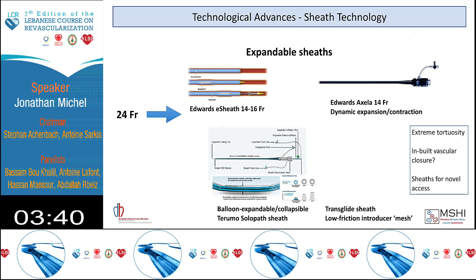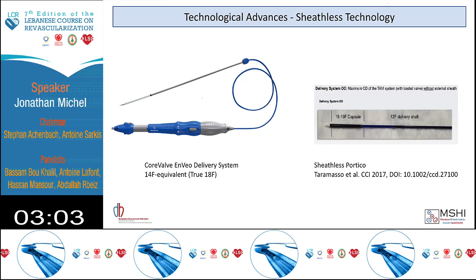Sheathless technology, of course, is on the market as well. Although it's billed as sheathless, I do point out that there is a sheath that's built onto the catheter system of the CoreValve Evolut delivery device. This does give you a true 18 French, so 18 French is the size of the hole you put in the vessel, which is a little bit better than putting in a rigid sheath. The one downside to this particular valve is if you do need to post-dilate, then you have to take everything out, leave your wire in the LV, replace the sheath into the femoral artery, and then pass a balloon through.